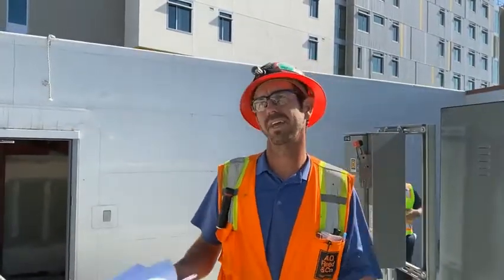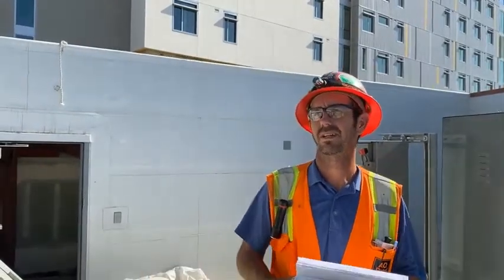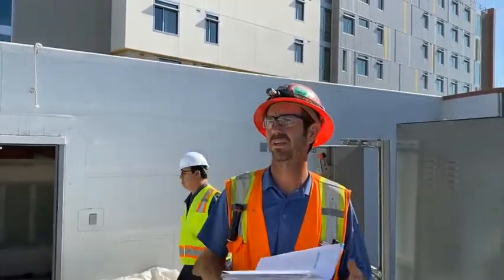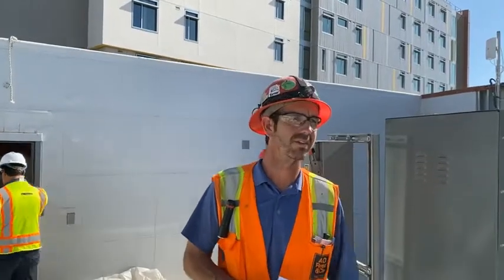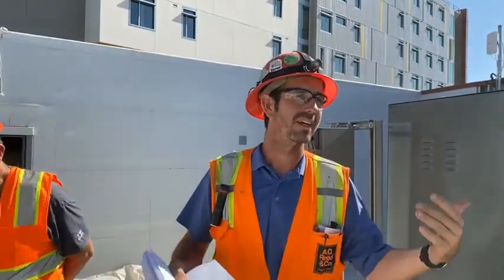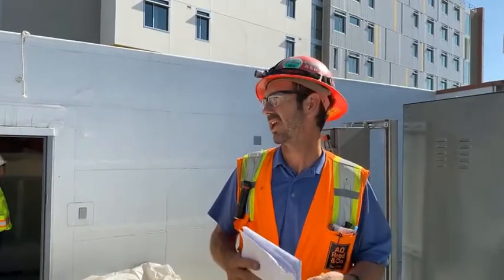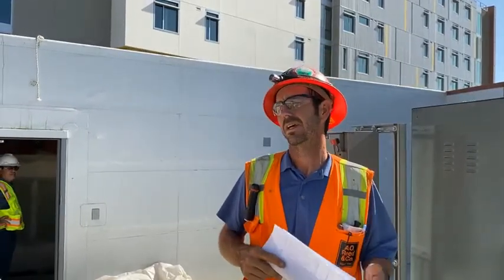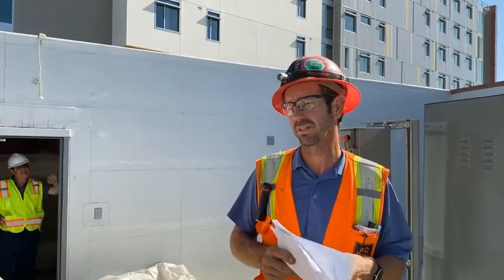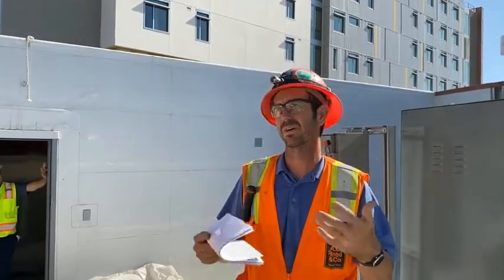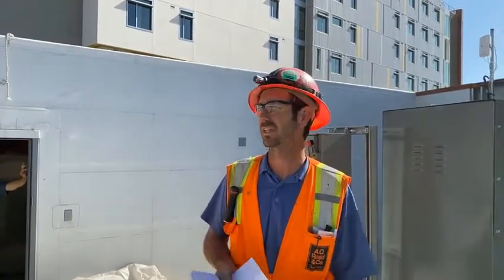okay? Any questions on the fans or the air handlers up here? Filter changes are going to be the most important thing for the air handlers, and making sure the drives are in auto. And then cleaning out the unit as necessary if there's dirt or debris in it. Clean out the condensate drains, condensate traps. Condensate traps and drains you'd probably want to inspect quarterly again. Make sure there's nothing developing in any of the drain pans.